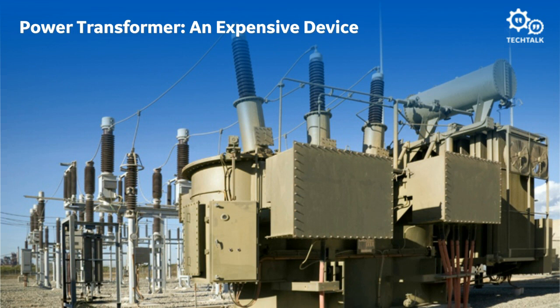Transformers are one of, if not, the most critical and expensive asset in a substation. If your transformer fails, basically everything downstream of it is affected. Designed-in redundancy is common in some form, but very rarely will people keep spares on hand since, again, they're expensive to buy and upkeep, and well, they don't exactly fit in a stock room. There's also usually a long lead time to repair or replace the transformer.